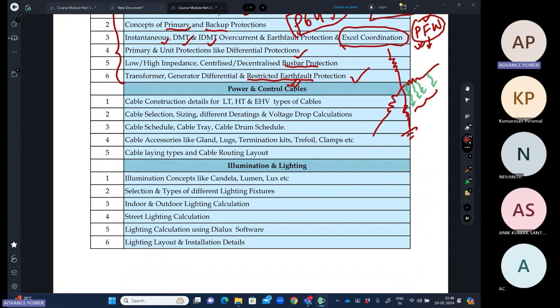After this, we'll discuss power and control cables. First we'll discuss the construction details. Sometimes it is in an engineer's mind that I am not manufacturing the cable, and most of the technologies are with the manufacturers, so I will be depending on the manufacturer for the cable I am selecting. But it's wrong. Mostly, 90% of the engineering will be done by the design engineer.